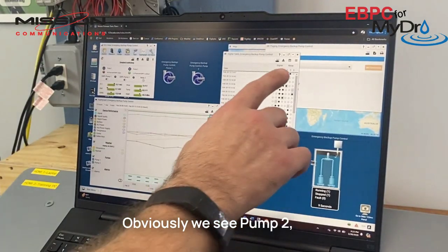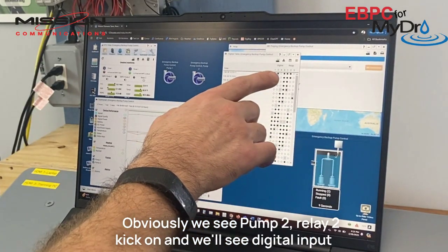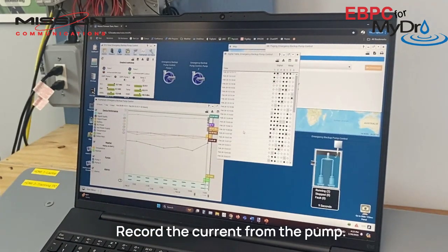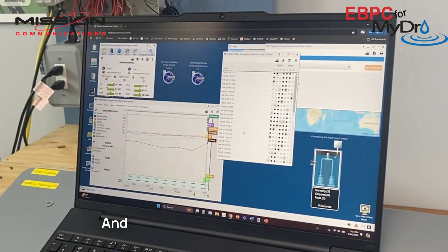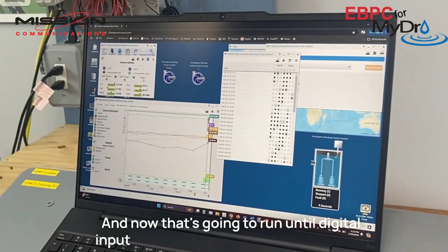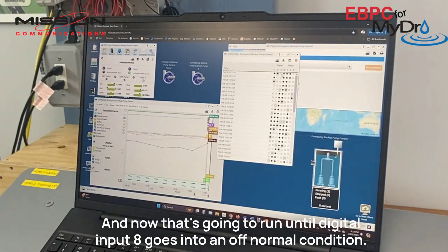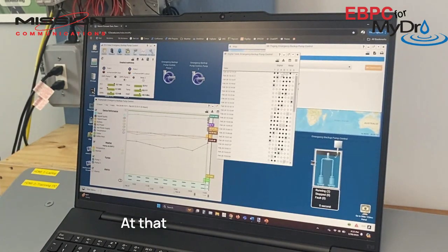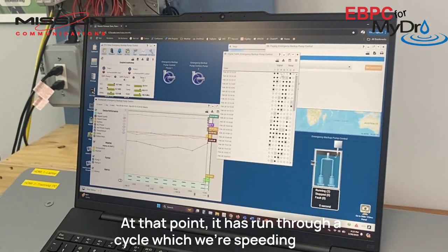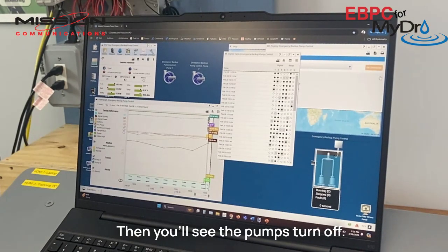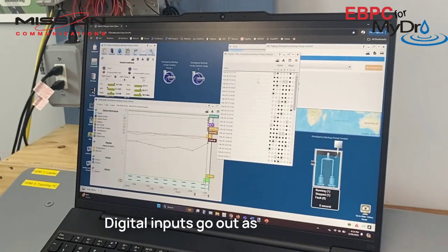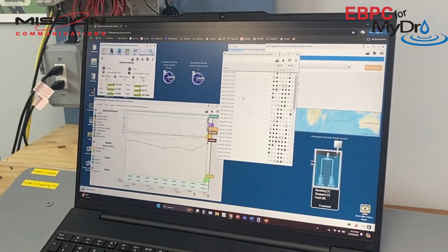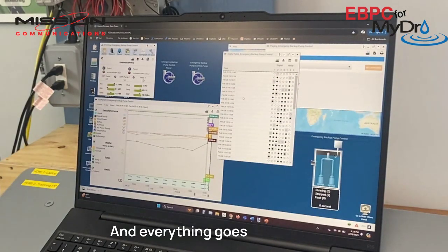Obviously, we see pump 2, relay 2 kick on. And we'll see digital input 2 record the current from the pump. So that's looking good. And then that's going to run until digital input 8 goes into an off normal condition. At that point, it has run through a cycle, which we're speeding this up. Then you'll see the pumps turn off, digital inputs go out as the AC current detectors no longer detect current. Everything goes back to normal with your inputs 4 and 8.